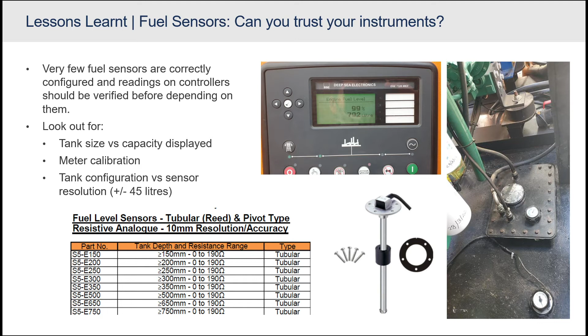If we go to the next slide, that is a typical configuration of a tank on the left-hand side. What we often see is that those fuel sensors come in specific lengths, and it doesn't necessarily cater for your fuel tank. Quite often you take the one that is as long as possible, but we've seen a lot that are relatively short compared to the depth of the tank. For instance, that one is a representation of one of the real installations that we've got. If that fuel sensor comes to its bottom, where it shows 0, there's actually still 40% fuel in that tank. So you need to calibrate it. What is 100%, and what does it mean when that sensor reaches its limit at the bottom? Is it really 0 or is it actually 40%?